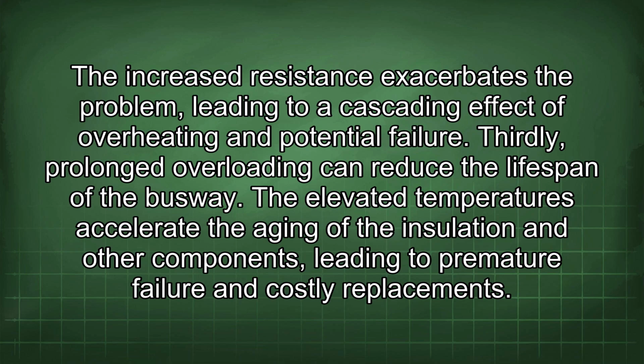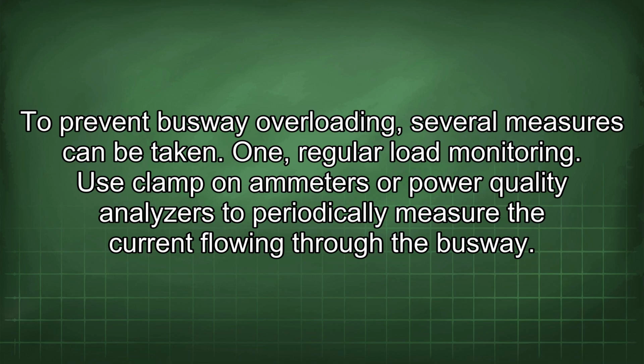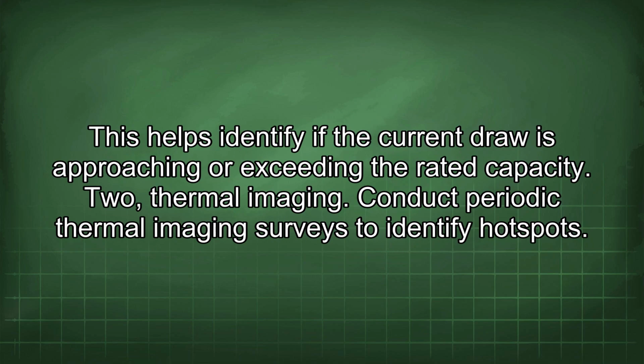Thirdly, prolonged overloading can reduce the lifespan of the busway. The elevated temperatures accelerate the aging of the insulation and other components, leading to premature failure and costly replacements. To prevent busway overloading, several measures can be taken. 1. Regular load monitoring. Use clamp-on ammeters or power quality analyzers to periodically measure the current flowing through the busway. This helps identify if the current draw is approaching or exceeding the rated capacity. 2. Thermal imaging. Conduct periodic thermal imaging surveys to identify hotspots.